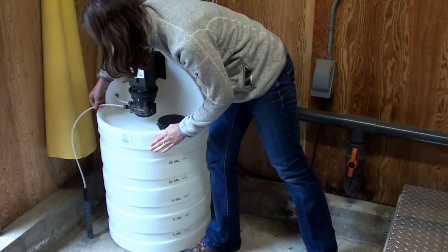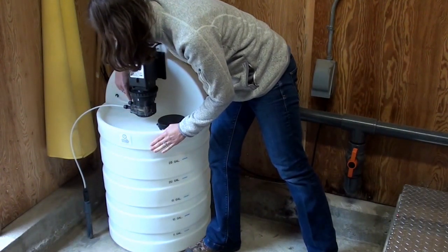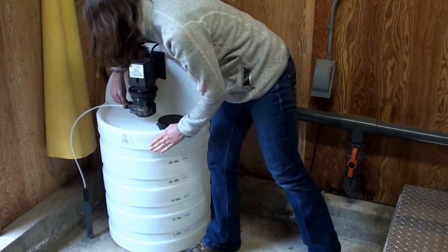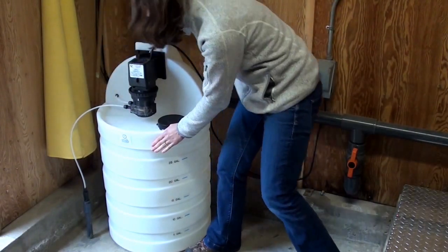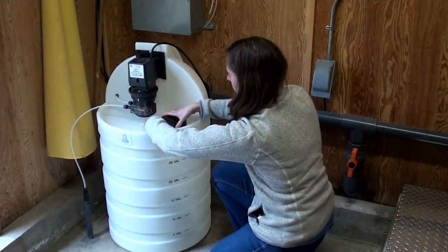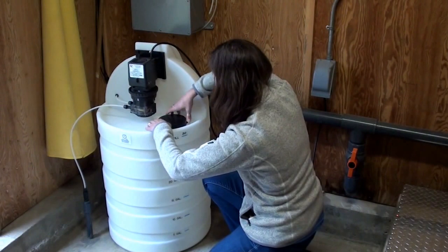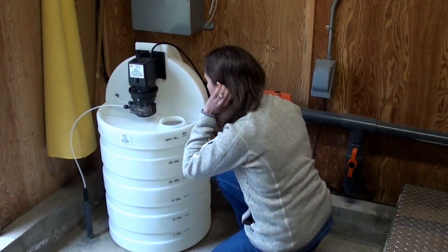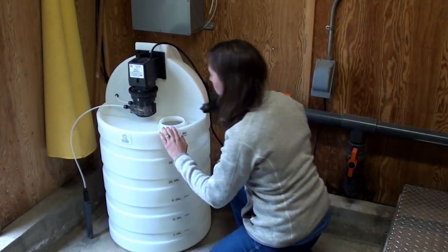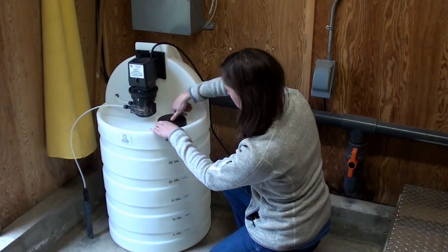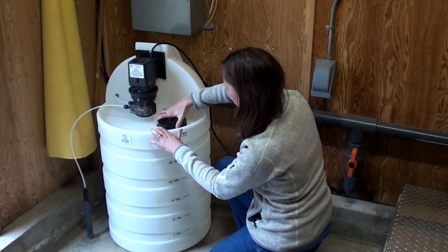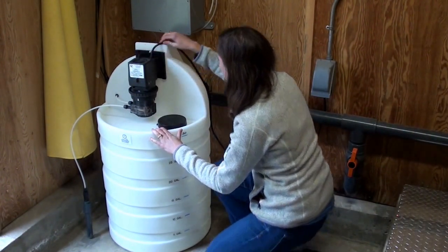Treatment bypasses may occur if valves are accidentally turned, so this is a good time to assess the current configuration to make sure the integrity of the system is being protected. Walk through the treatment plant. Make sure that all of the chemicals being used are in good condition, that the chemical storage tanks have sufficient volume, and that the chemical feed pumps are working properly.